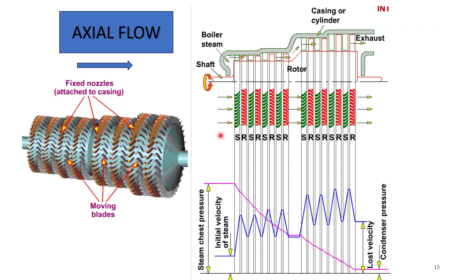Almost all multi-stage turbines are axial flow turbines, meaning the flow takes place in the direction of the shaft or in the longitudinal direction. There are numbers of fixed (S) and moving (R) blades where pressure continuously drops stage-wise. In every fixed nozzle, pressure drops and velocity increases, and on the reaction side this happens in both fixed and moving blades — that is how steam flows through the turbine.